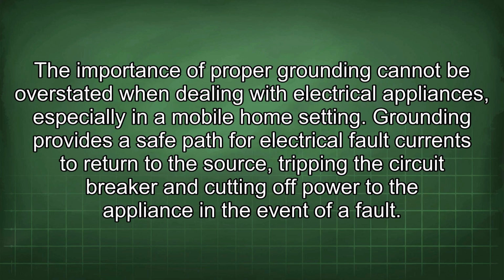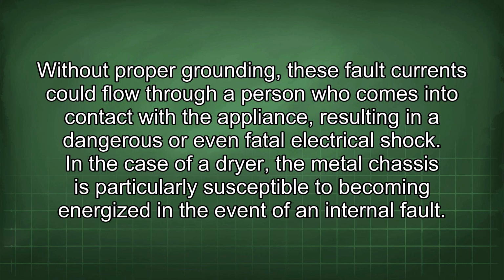The importance of proper grounding cannot be overstated when dealing with electrical appliances, especially in a mobile home setting. Grounding provides a safe path for electrical fault currents to return to the source, tripping the circuit breaker and cutting off power to the appliance in the event of a fault. Without proper grounding, these fault currents could flow through a person who comes into contact with the appliance, resulting in a dangerous or even fatal electrical shock.